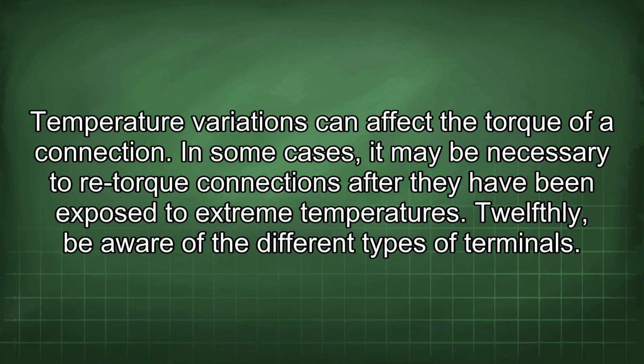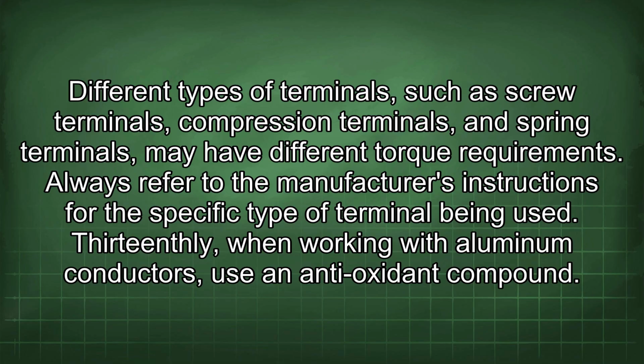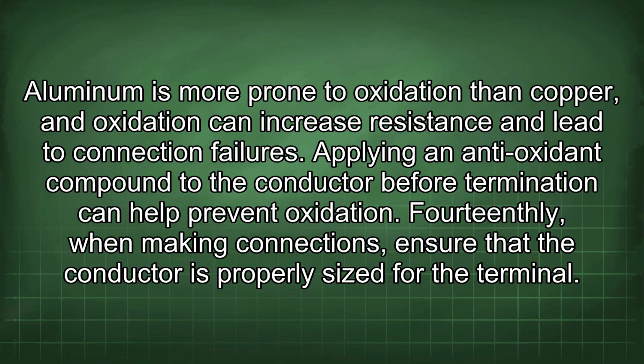Twelfthly, be aware of the different types of terminals. Different types of terminals, such as screw terminals, compression terminals, and spring terminals, may have different torque requirements. Always refer to the manufacturer's instructions for the specific type of terminal being used. Thirteenthly, when working with aluminum conductors, use an antioxidant compound. Aluminum is more prone to oxidation than copper, and oxidation can increase resistance and lead to connection failures. Applying an antioxidant compound to the conductor before termination can help prevent oxidation.